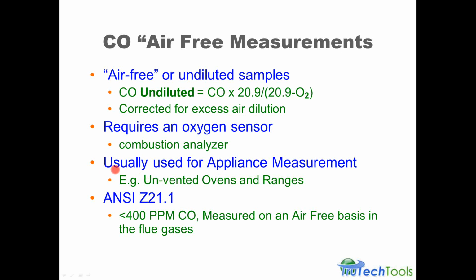But it's also gaining some popularity and being used for in-stack measurement because it does get rid of that variability that comes from the changing oxygen levels. And it does relate to an ANSI standard, American National Standards Institute Z21.1 standard, where we talked about already less than 400 parts per million measured on an air-free basis in the flue gases for most appliances.